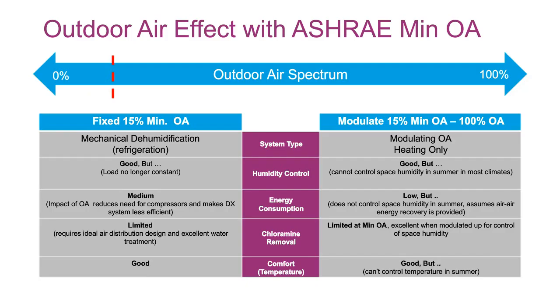So what is the effect of the ASHRAE minimum outside air on the pool? Well, if we had a fixed 15% minimum, the mechanical refrigeration system is going to have good humidity control. Not quite as good as if you had no outside air, because now you're starting to affect the conditions a little bit. Energy consumption goes from low to medium because now the outside air reduces the need for compressors. As we said, anywhere from 5 to 7 months, 8 months, depending on where you are climate-wise. And it makes the DX system low, not at full load, and less efficient.